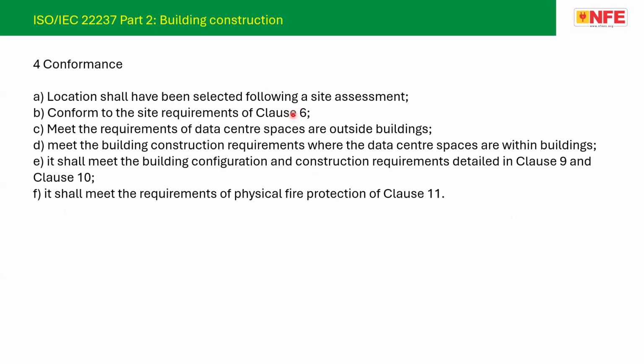Now, in every part of 22237, clause 4 talks about conformance. As I said, conformance means compliance. Whatever is written in this standard or in this clause must be complied with. For example, for building construction, the location shall have been selected following site assessment, with conformance to site conditions of clause 6 of this particular standard, meeting the requirements of data center space outside the building and space inside the building, and it should meet construction requirements as per clauses 9 and 10, and fire safety requirements as per clause 11.